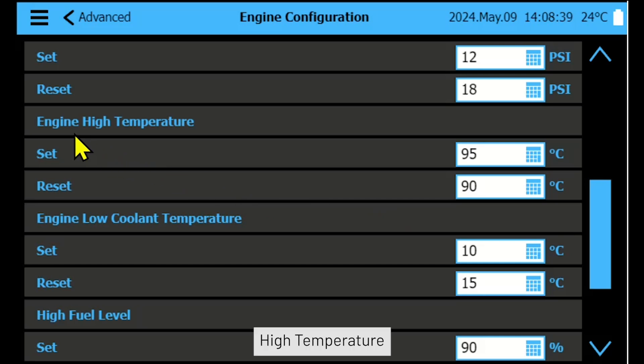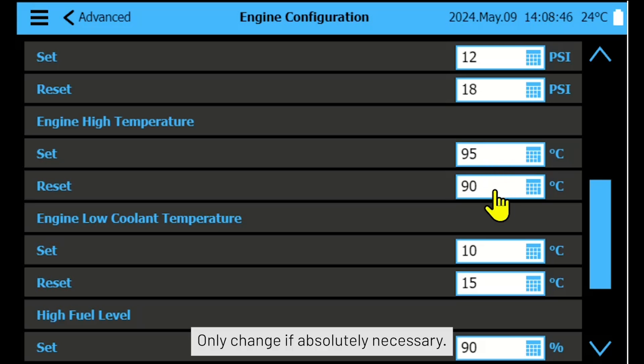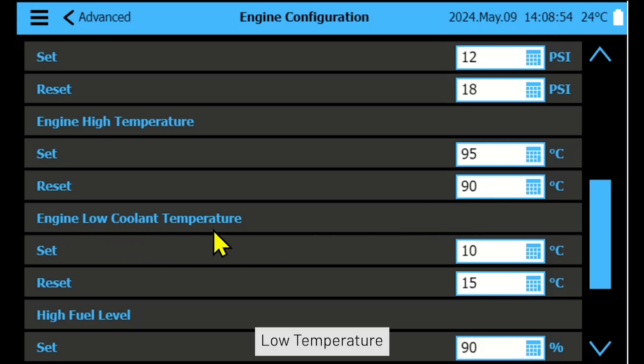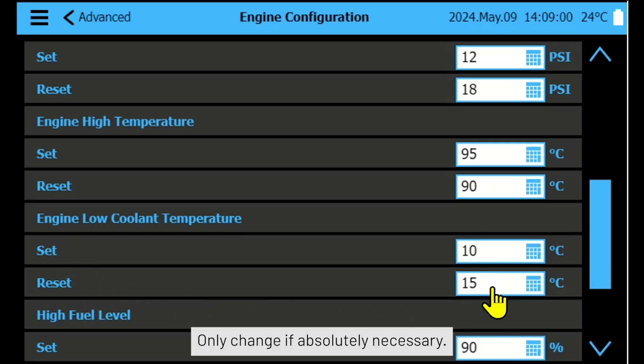High temperature: set and reset points are factory set to 95 degrees Celsius and 90 degrees Celsius — only change if absolutely necessary. Low temperature: set and reset points are factory set to 10 degrees Celsius and 15 degrees Celsius — only change if absolutely necessary.